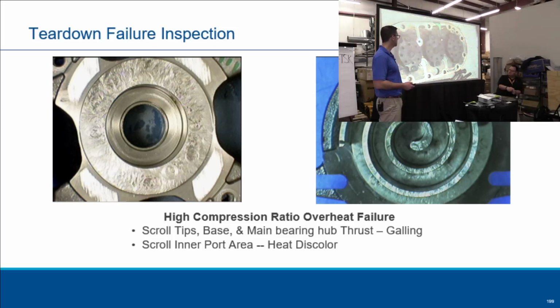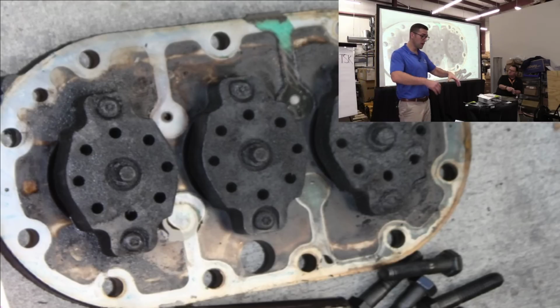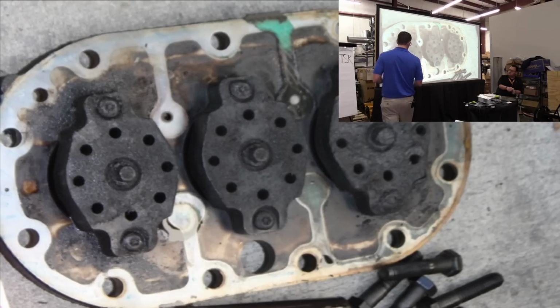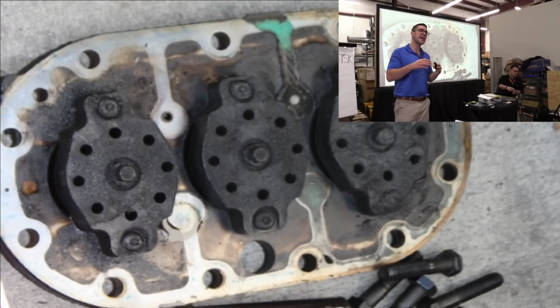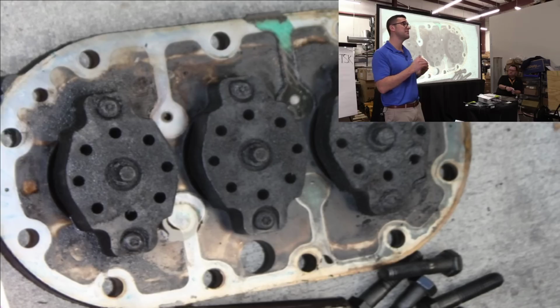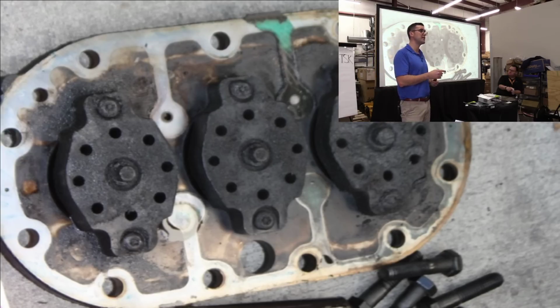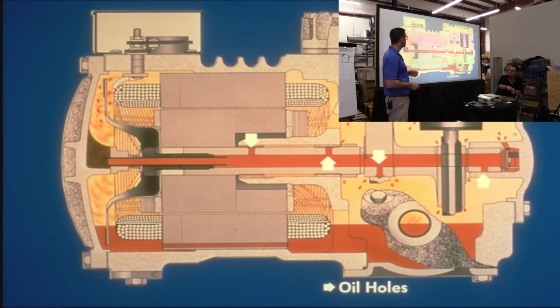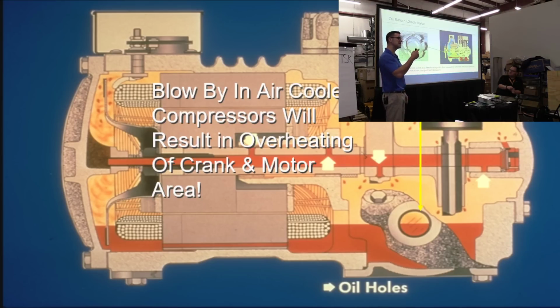No. Okay. Heads. If you pull off the head and it's super black like this and you can't rub it off, that is major, major overheat. But if you pull off a head and you can rub it off and it cleans off, that's mechanical wear. That's your bearings, that's your wrist pins. Something is wearing in there causing your oil to turn black. Okay, blow-by. You get the overheat, it wears your cylinder walls, and it causes overheat to the crank and motor. And air-cooled compressors. So let's get to this point. I talked about it earlier.